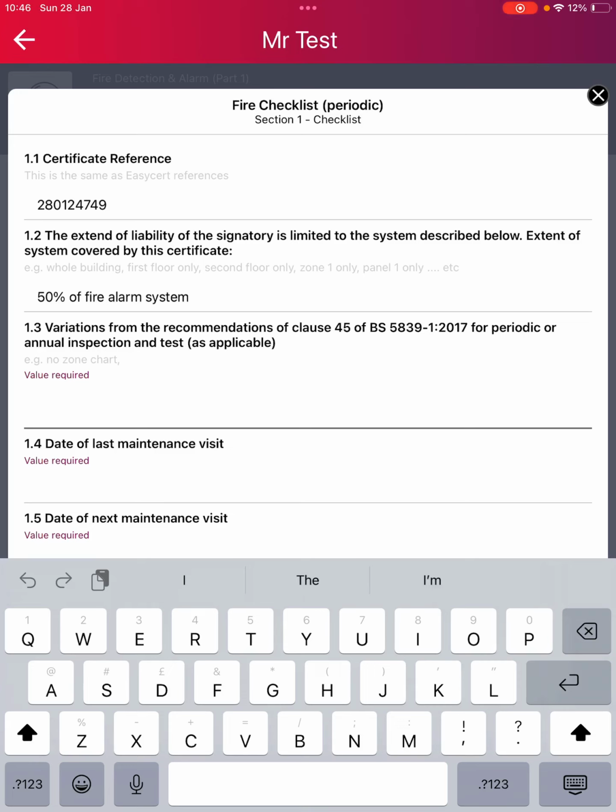It also says multi-sensor fire detectors should be physically tested by a method that confirms that the products of combustion in the vicinity of the detector can reach the sensors and that the appropriate response is confirmed by the CIE, which is the panel basically. The CIE is the panel. I always forget what that acronym stands for. Control and indicating equipment. That's it. As well as that, so test every device.